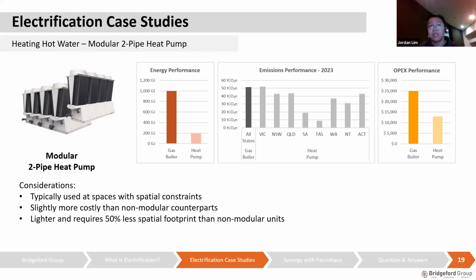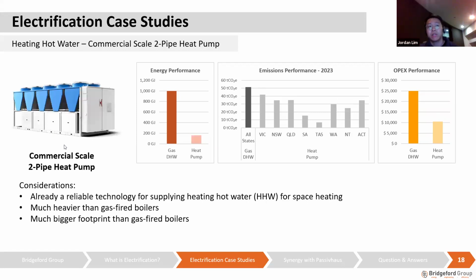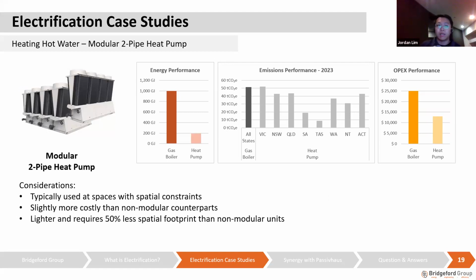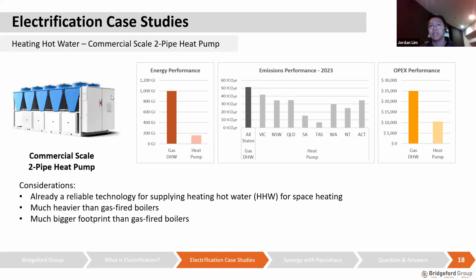The reason why the efficiency is lower compared to a commercial scale heat pump like this one is because modular heat pumps are typically staged. That means one heat pump will first have to fulfill its peak capacity, then the second one will start running. So if you have a system where 4 modular heat pumps are running at the same time, 3 of them are running at peak capacity. And as we explained earlier, when heat pumps are running at peak capacity, the efficiency is at its very lowest. It's only the 4th unit, as in my example earlier, that will be running on part load. That's the reason why the overall efficiency of modular 2-pipe heat pumps is lower than these big units over here.